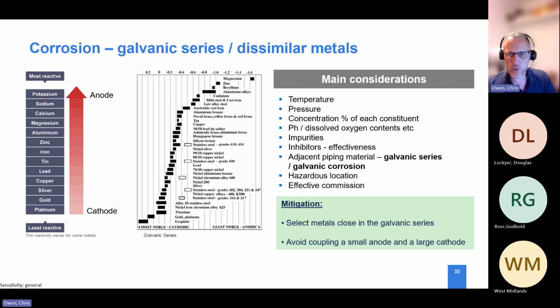But we saw a lot of people switch across to stainless steel with the belief that stainless steel didn't corrode and they could have these thin wall tubes. The problem is that stainless steel does corrode, but more importantly, it's more cathodic in what we call the galvanic series. So stainless steel can be used in process pipework, catering pipework, where the rest of the system is also stainless steel. When you see stainless steel being used in building services, normally there are other materials such as carbon steel or copper in those pipework systems. So we call them mixed metal hybrid systems.